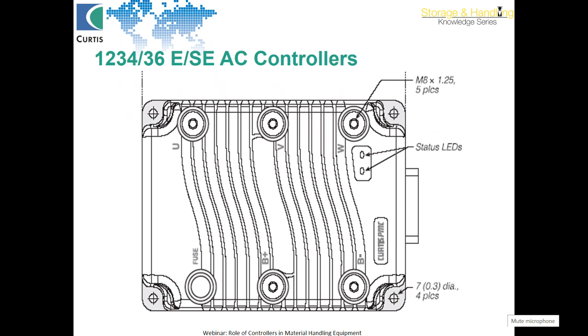Very important here is, when you replace the controller in the field, or at the time of manufacturing equipment, you have to be very careful about what kind of fixtures and hardware you are using and in what order. The lug has to be placed on a power terminal before anything else. On top of it, we recommend a Schnorr or equivalent washer, which is called a safety washer, with a convex side on top, so that it holds the bolt tightly against the vibrations of the moving equipment. Tightening torques have to be followed ideally.